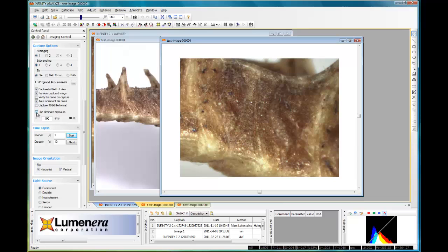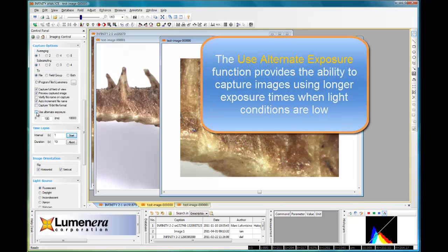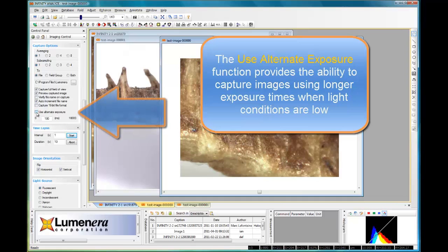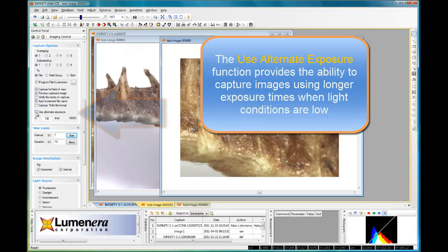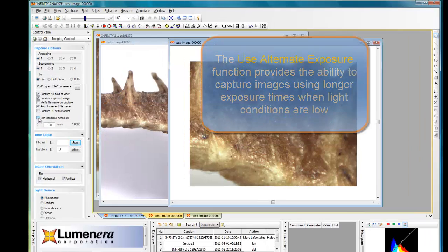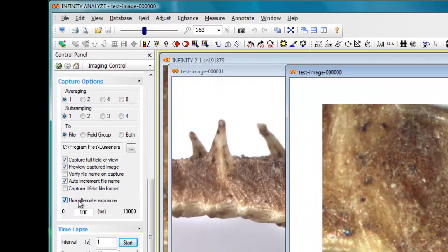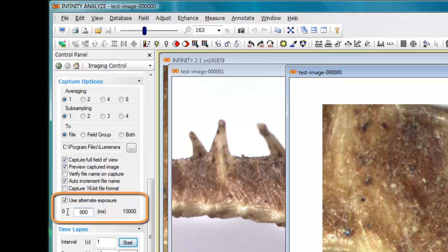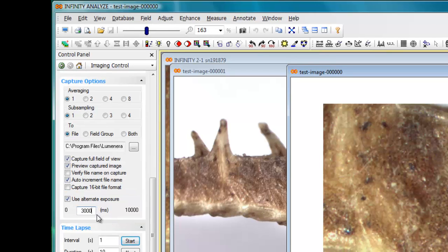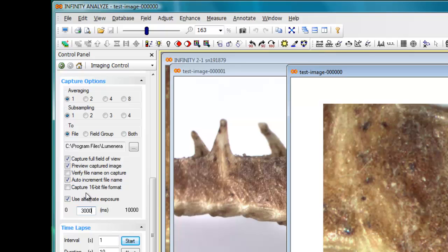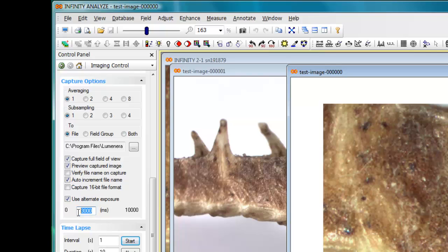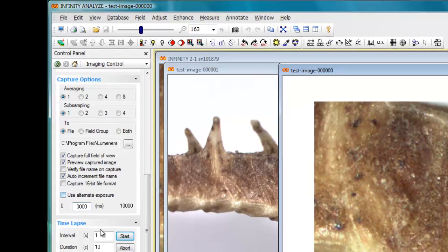Under certain application conditions, you can get enough light for your bright field images, but when you capture an image after focusing it on the live preview, you may want to switch to a fluorescent lamp and you may want to do a longer exposure. So selecting this use alternate exposure checkbox and putting in a value in milliseconds that you want. So 3000 milliseconds will give you a 3 second exposure. So now each time I click the capture button, I'm going to get an exposure time that would be 3 seconds long if that's what I've specified as my alternate exposure.